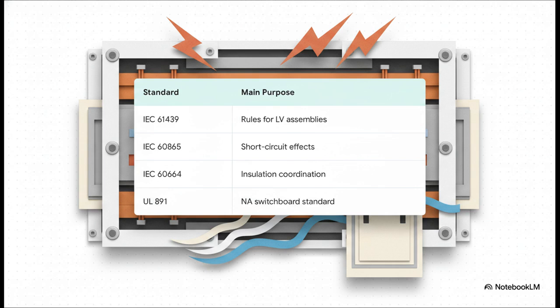Now, what's really interesting to note here is the core philosophy. Design verification belongs to the complete assembly. You literally cannot just declare a generic fault rating based on an isolated copper bar. That declared withstand capacity has to be verified for the conductors, the supports, the enclosure, and the joints all working together as one tested system.